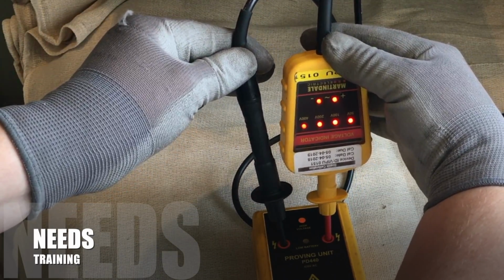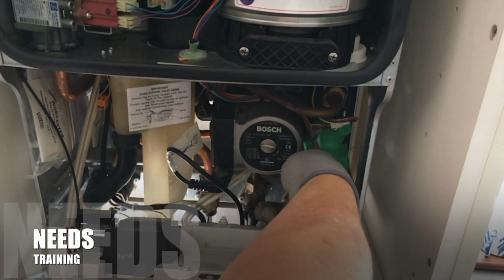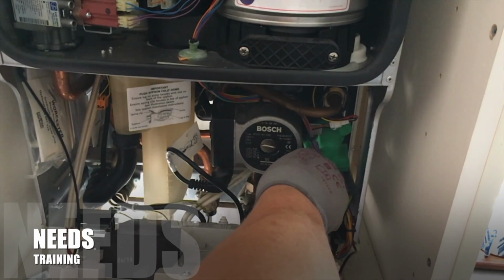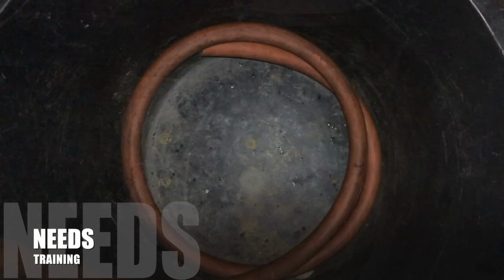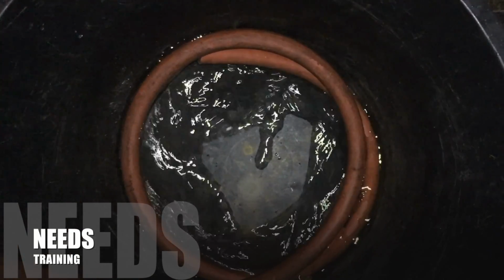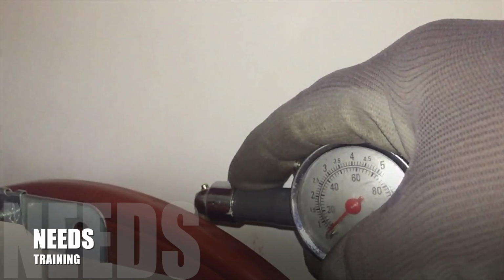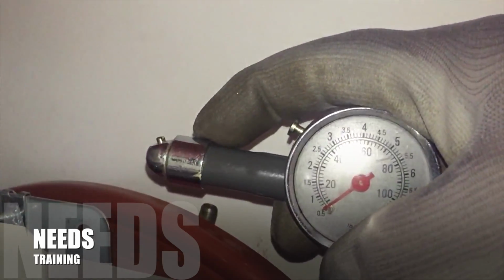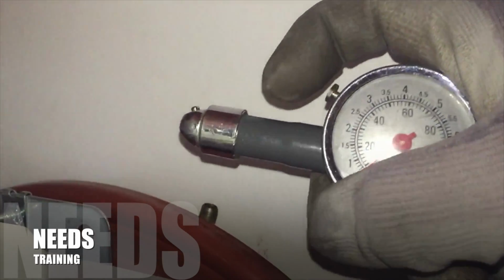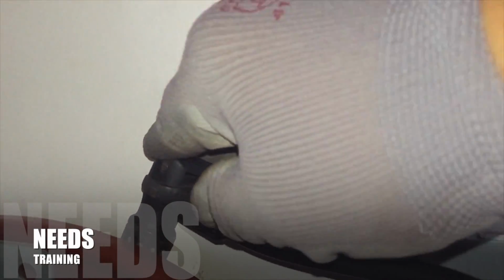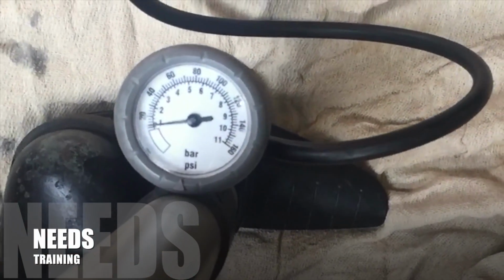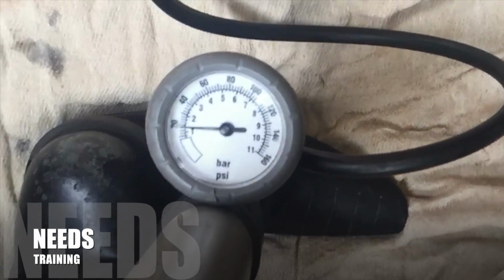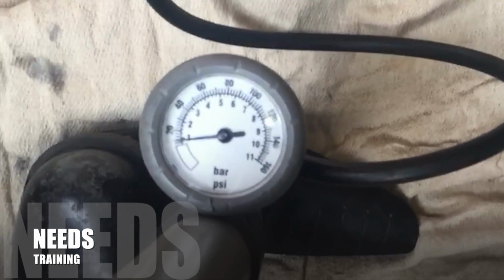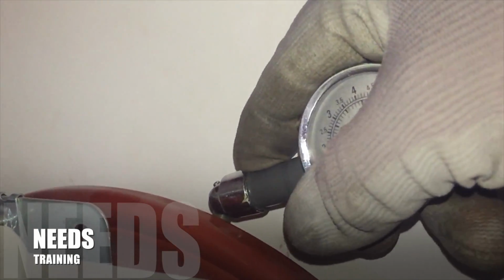Now that you have completed the checks, depressurize the appliance by using the drain point. Now test the expansion vessel with a pressure gauge. The expansion vessel pressure should be between 0.5 of a bar and 1 bar. Repressurize the expansion vessel to 1 bar. With some leak detection fluid, check Schrader valve is not leaking.